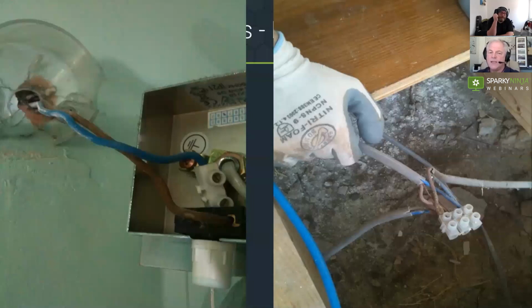Okay, that's a laminated floor. You're not going to be able to take that up for maintenance. So we agree it needs to be enclosed. It's a C2 because it's not enclosed in the space that it's in. There's no fault protection on those load conductors again, and the actual connection needs to be a fixed connection, a maintenance-free connection if it's just under the boards with no accessible hatch.